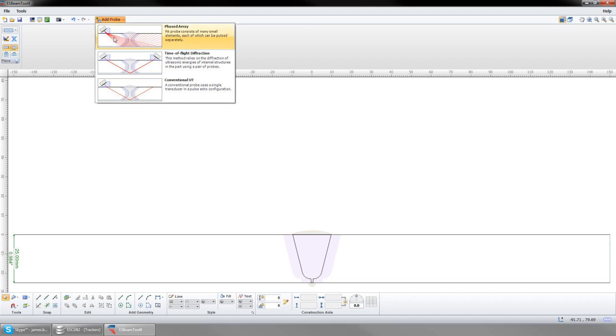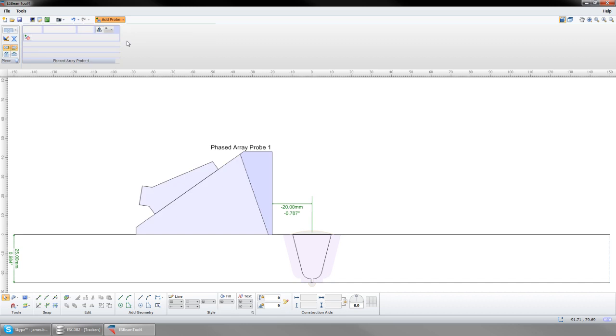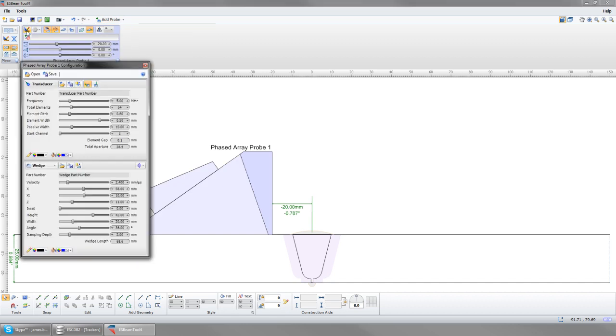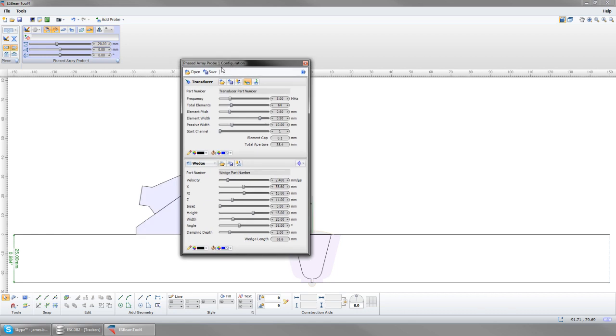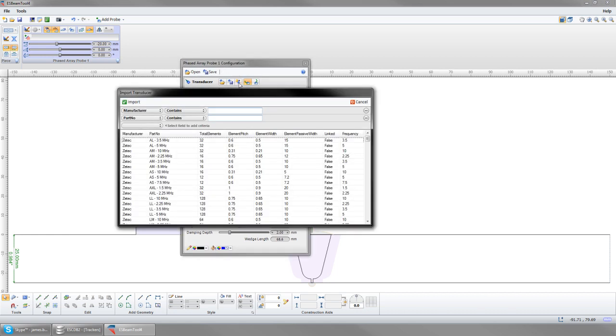A default probe will appear in the workspace. To change the probe setup, select the probe configuration icon. Here you can manually modify the transducer and wedge specifications, or import them from the ESBeamTool library.